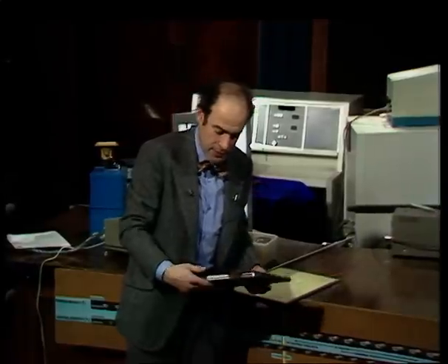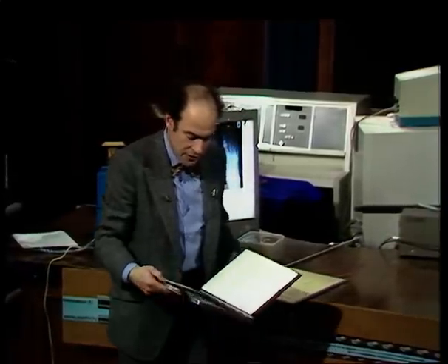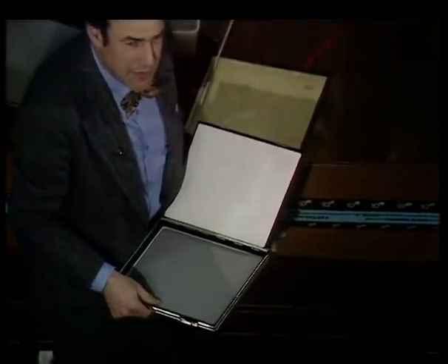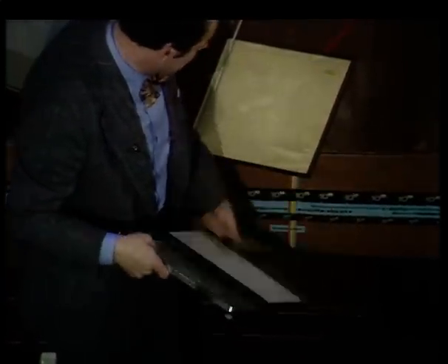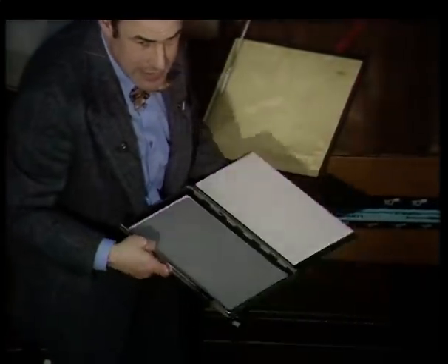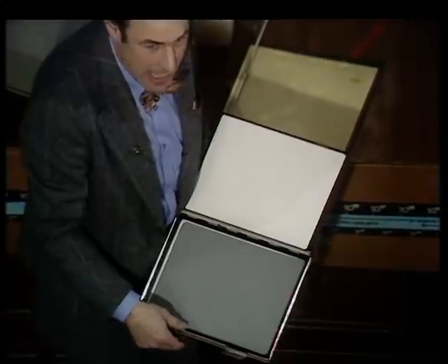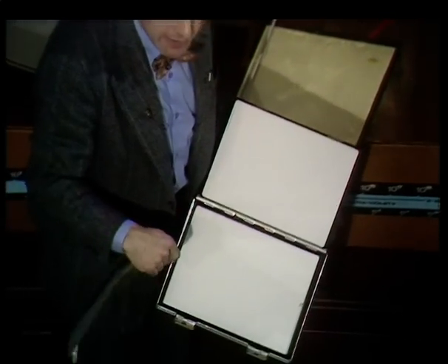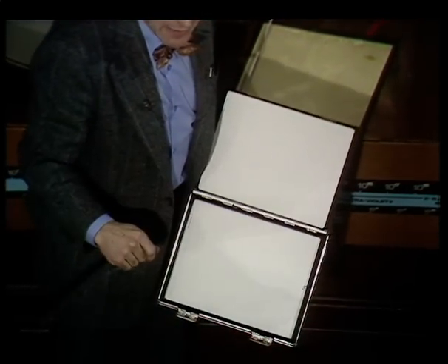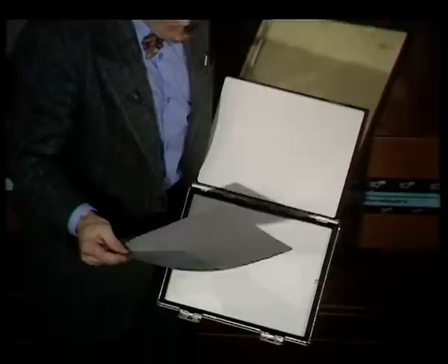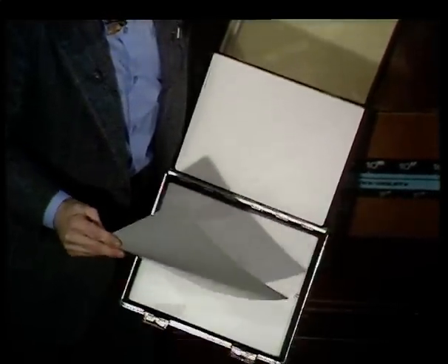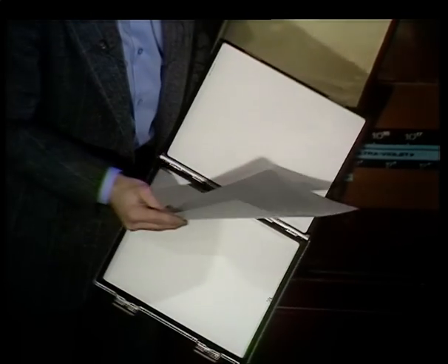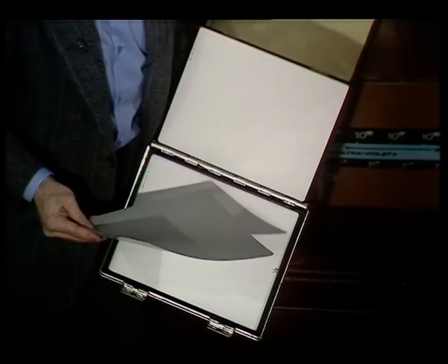But the next development was to make use of the fact, or to combine the effects of the fluorescent screens, which I've already shown you just now, and the sensitivity of film both to X-ray and light, by sandwiching the film between two screens which are made of this fluorescent material. So that this film, in addition to being affected by the direct beam of X-rays, was also affected by the glow which was being produced by the so-called intensifying screens.